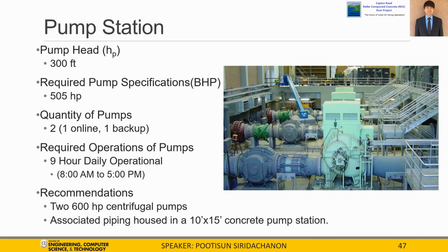For this pump station, there will be 2 pumps, with one being online and one being a backup. They are required to be operational for 9 hours daily from 8 a.m. to 5 p.m.